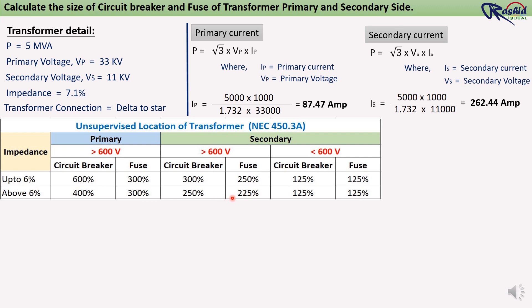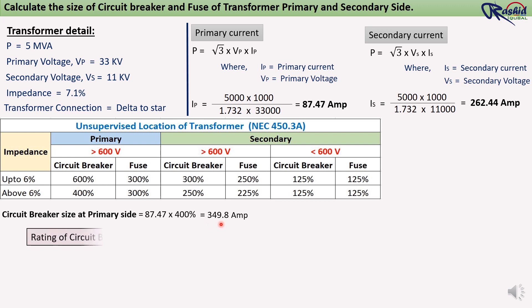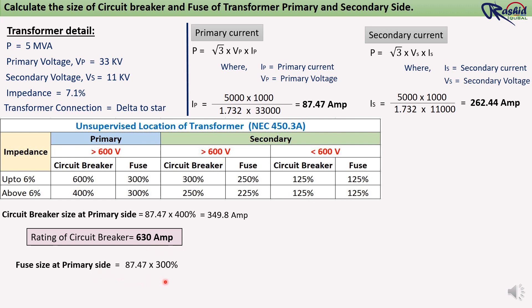For circuit breaker size at the primary side, we multiply 400% by the primary current: 87.47 × 400% = 349.8 ampere. Since 349.8 ampere is not available, we will use a 630 ampere VCB. For fuse size: 87.47 × 300% = 262.41 ampere. Since 262.41 ampere is not available, we go with a 300 ampere fuse.